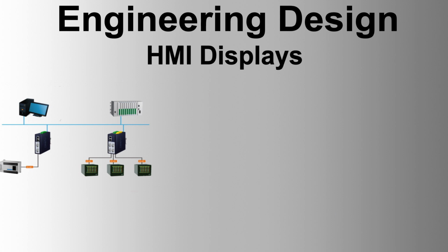Display navigation. General displays in the DCS can be accessed using console keys or through targets configured within the graphics. Navigation through different displays to take action resulting from an alarm should be achieved by a maximum of 3 commands. During the design and configuration of displays, clear navigation rules should be developed to ensure a consistent and structured approach in moving from one display to another. Stack display navigation and command tools.